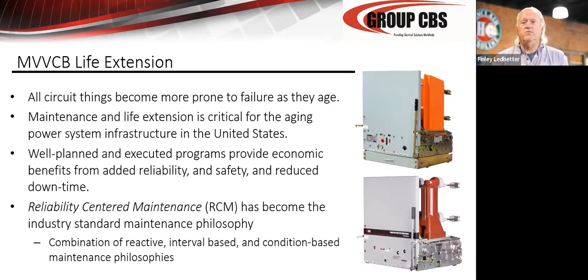So when you get a vacuum breaker that has in excess of about 3,000 operations on it, if you make it that far, typically you've got real mechanical problems and electrical problems. If you get to about 30 years old, you start to get all sorts of vacuum interrupter problems and materials problems. So maintenance cycles come into this. We're going to get into that shortly. The life extension of this critical infrastructure is very critical. A well-planned and executed maintenance program and safety program is really something you need to think about. Reliability-centered maintenance is key here, and it's become the industry standard.